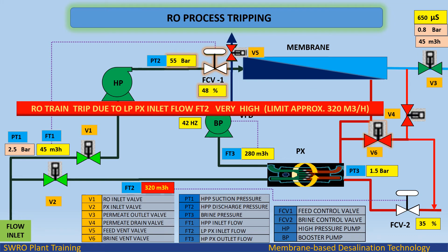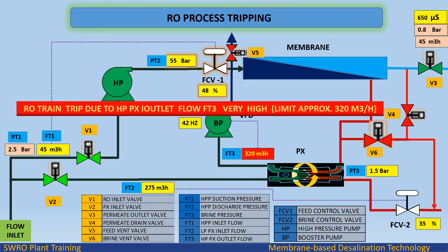RO train trip due to LP pressure exchanger inlet flow FT2 very high, limit approximately 320 cubic meters per hour. RO train trip due to HP PX outlet flow FT3 very high, limit approximately 320 cubic meters per hour.